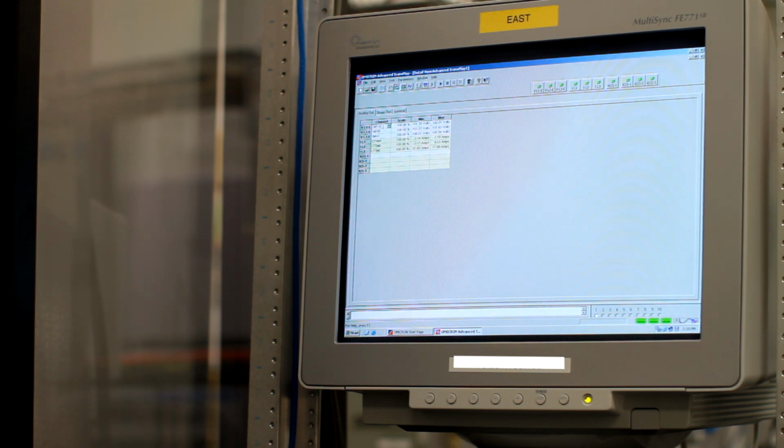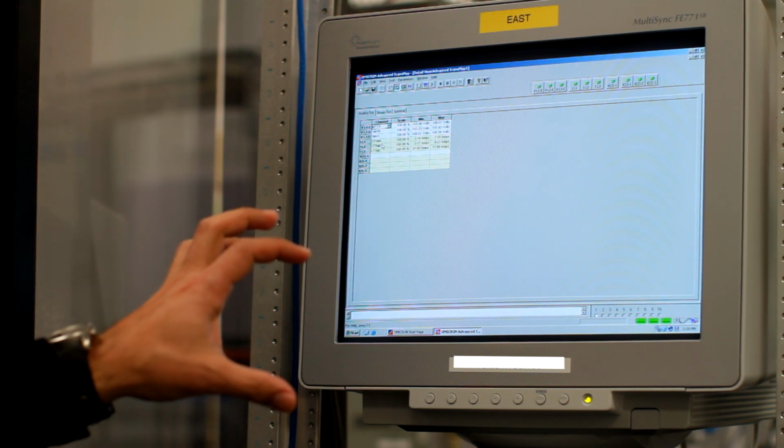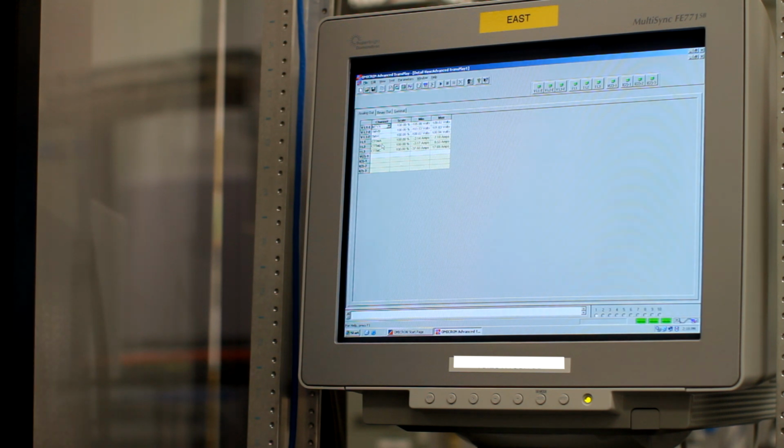So we're going to go in and change this. Now it's important to note that we need to roll B and C phases because the Omicron is not spaded into the test switches of the relays. So we have to go in here and make sure we roll B and C phase on potentials and currents, all the while making sure we're on the correct terminal.